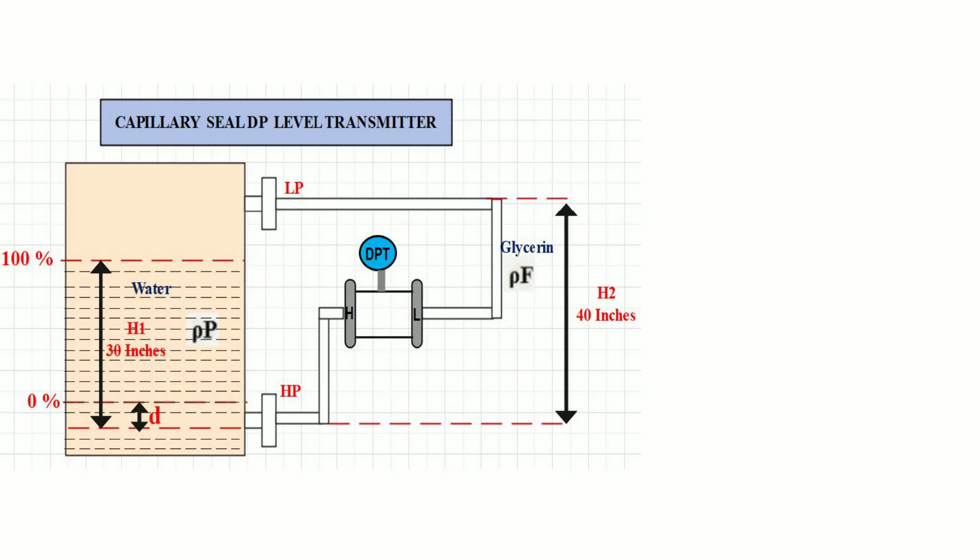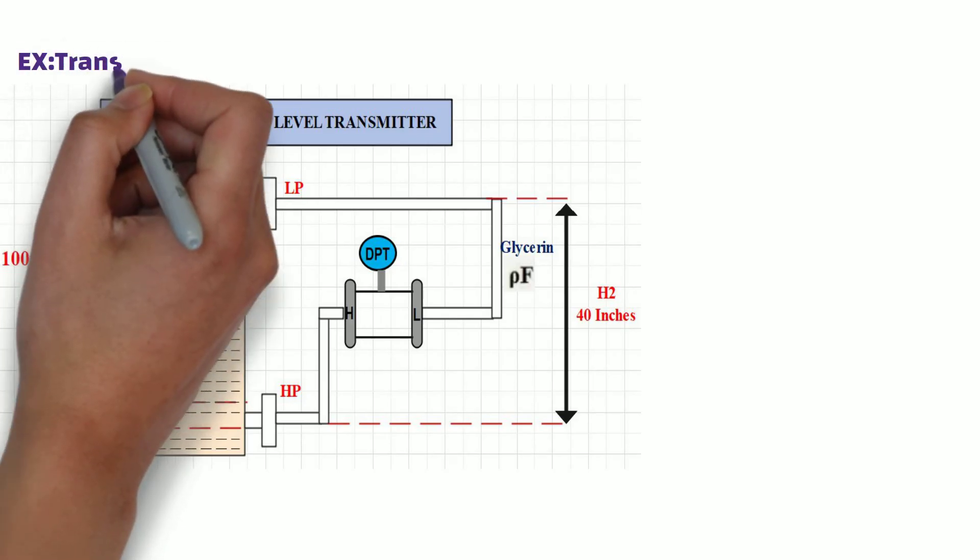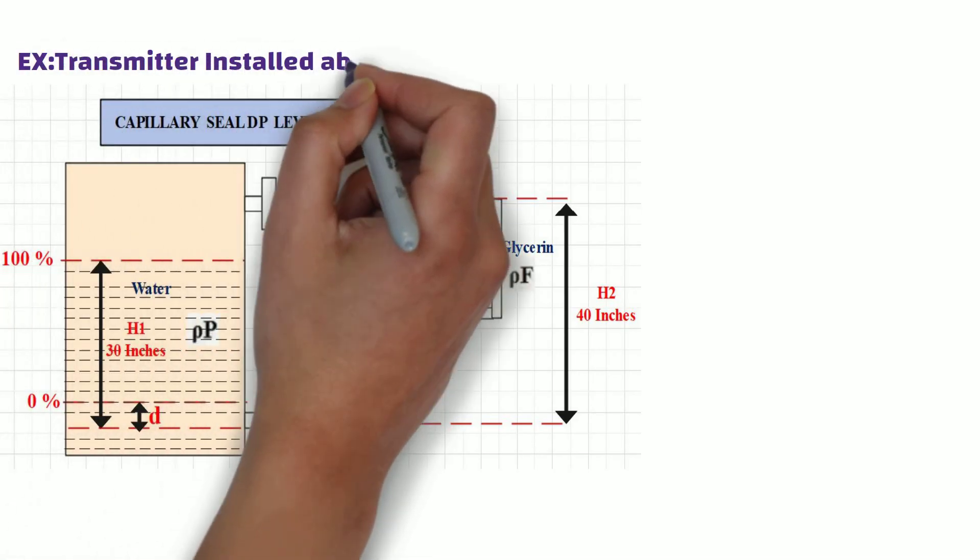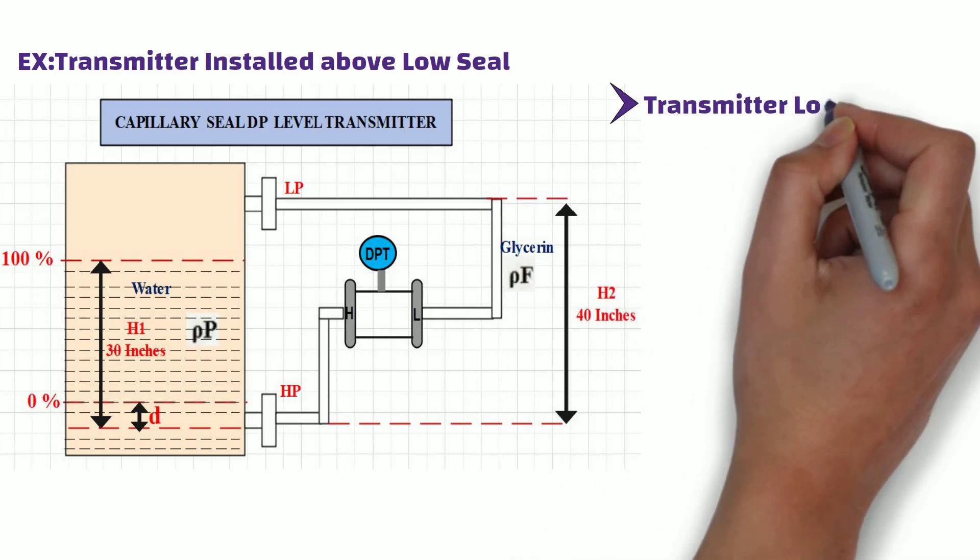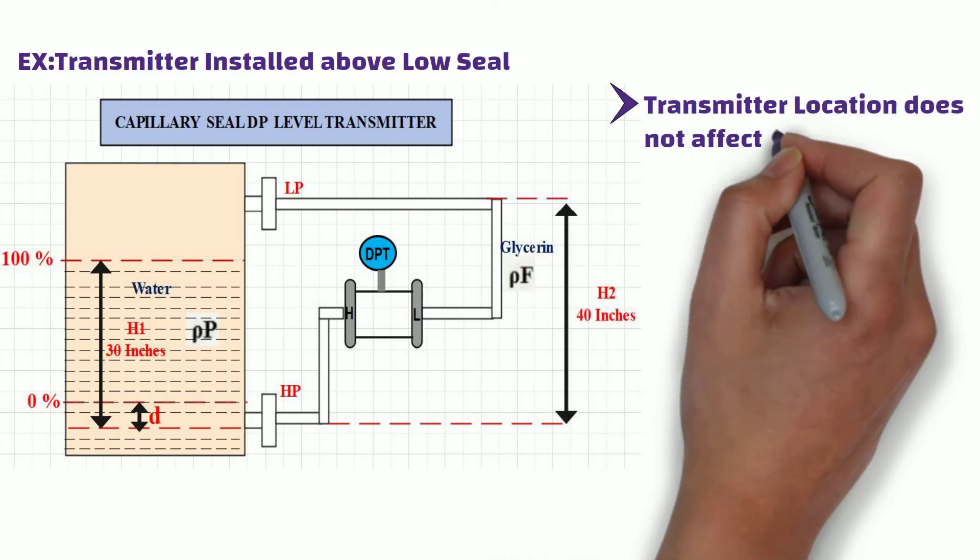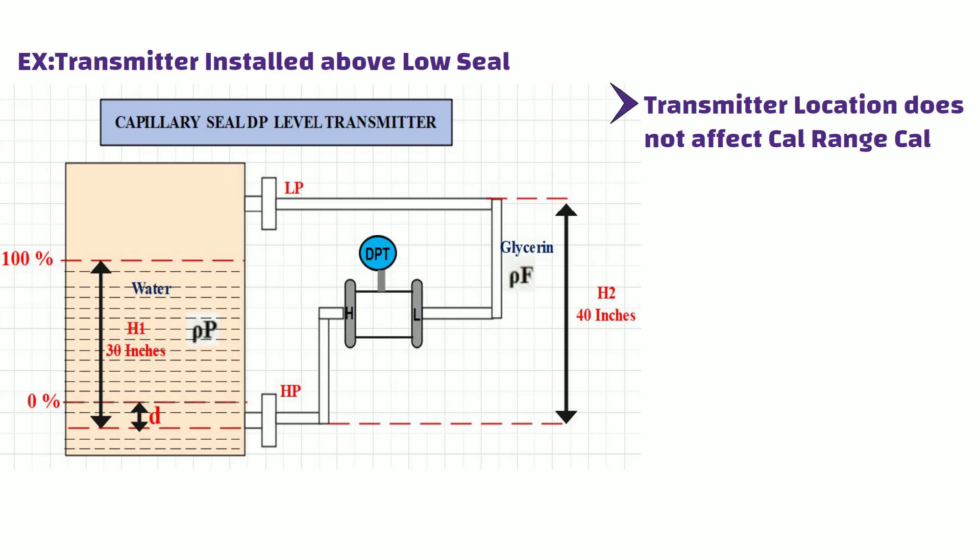As you can see, this is the example when the DP transmitter is installed above the low seal, and 0% level is also above the low seal. However, as we discussed earlier, transmitter location does not affect calibration range calculation when dual seals are used.